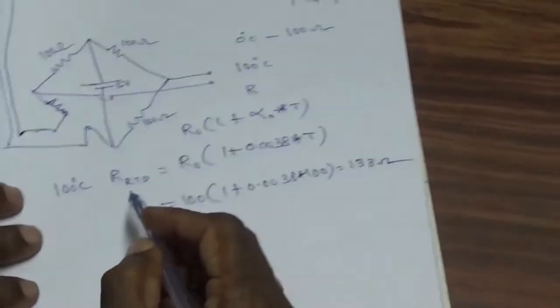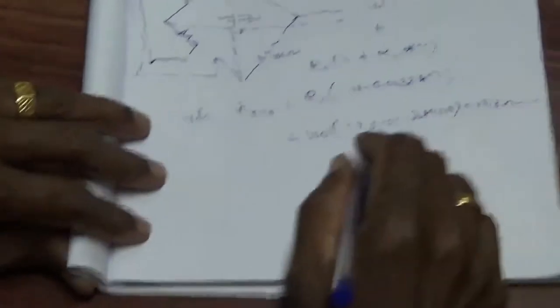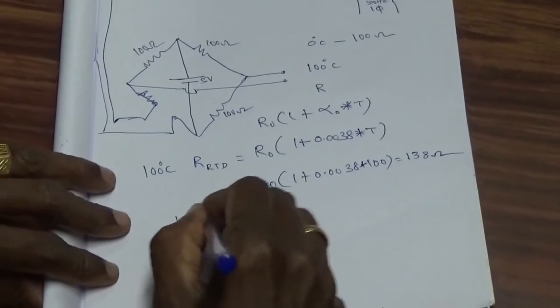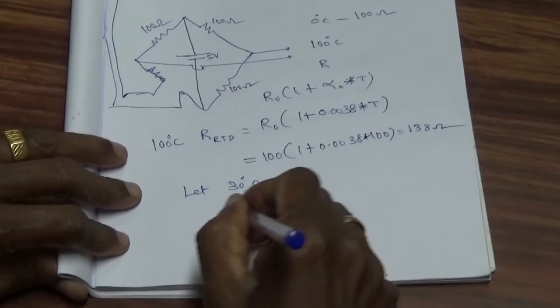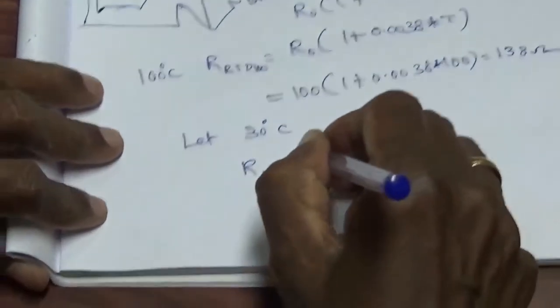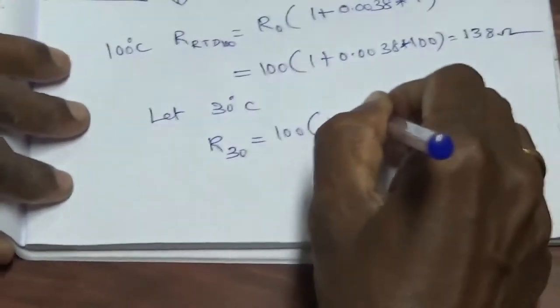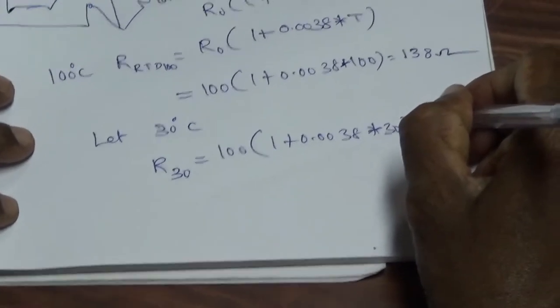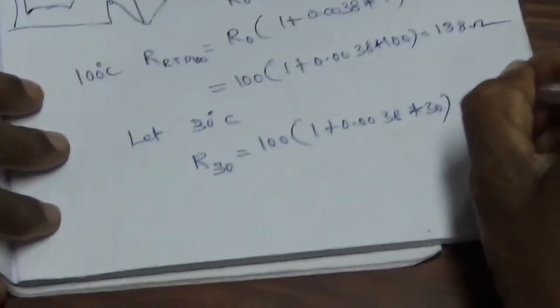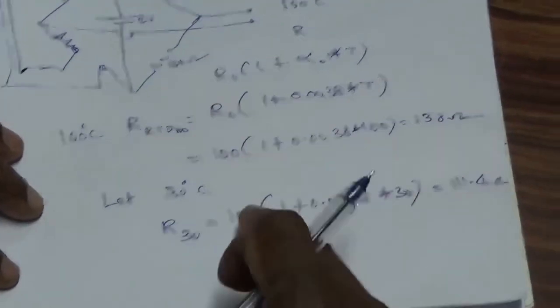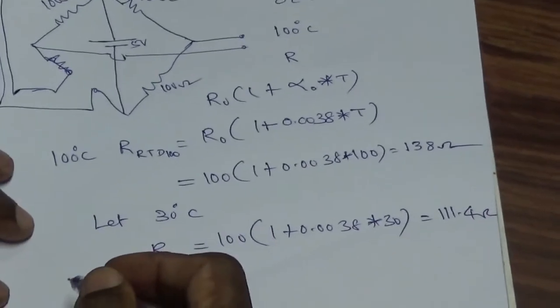Let us check the expected output of this bridge at room temperature and at 100 degrees centigrade. Let us assume room temperature is about 30 degrees centigrade. For 30 degrees centigrade, the RTD resistance R₃₀ = 100 × (1 + 0.0038 × 30), which comes to about 111.4 ohms. So what is the output voltage if the bridge is supplied with 5 volts?